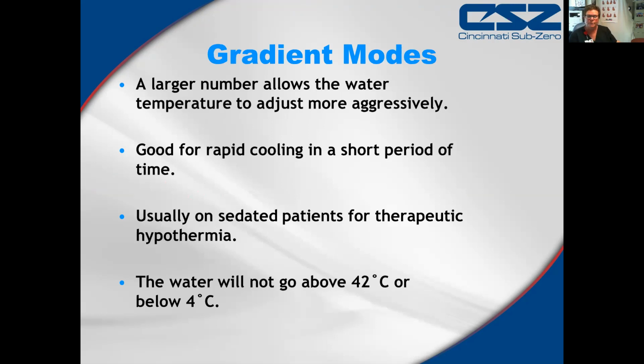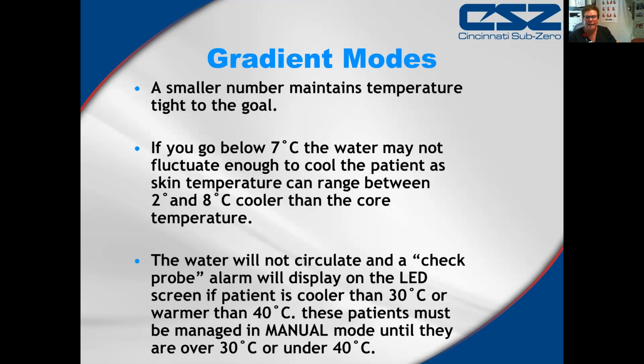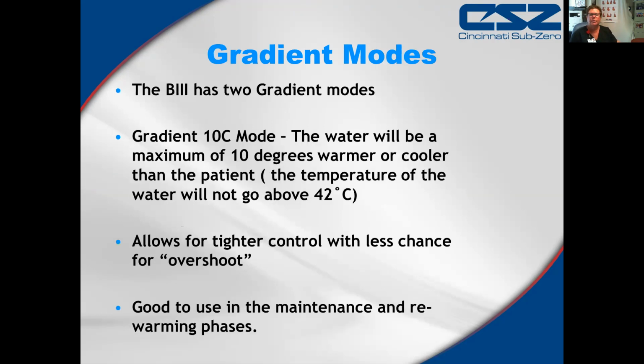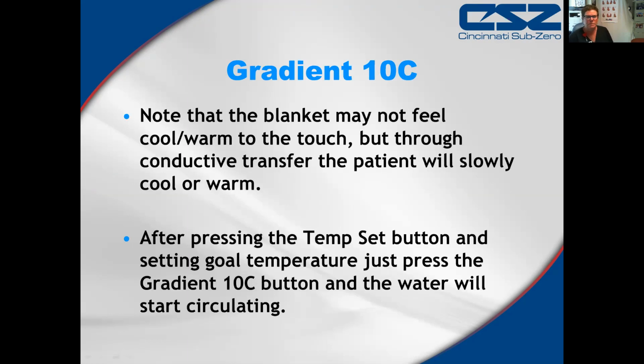If we were to use a mode called gradient 10, then our target temperature will be a maximum of 10 degrees warmer or 10 degrees cooler than our patient. But please keep in mind that our machine will only go to a max of 42, which is very warm, and to a minimum of 4 degrees. So the gradient modes allow for less overshoot, and they are good for the maintenance and the rewarming phases. So the gradient 10 smart mode is what I encourage people to use initially.